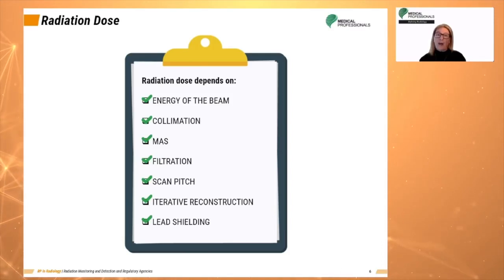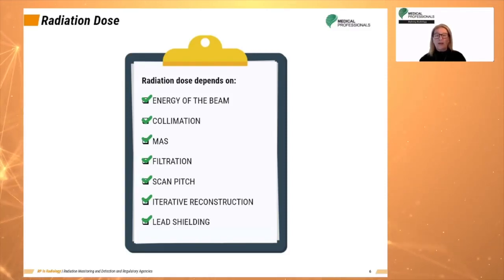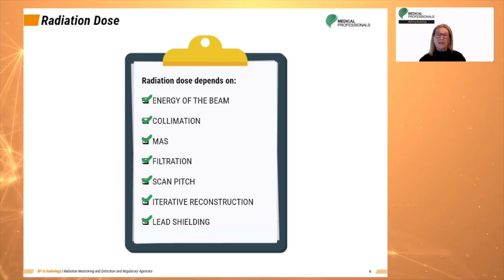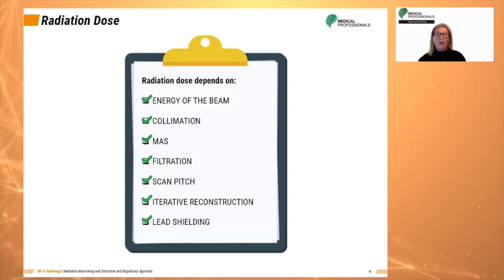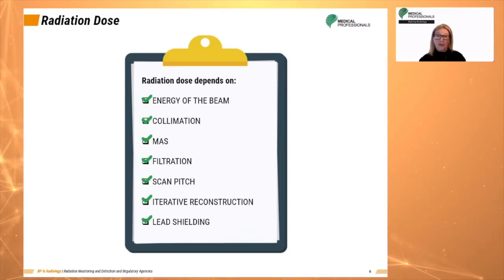The pitch is the way in which the continuous spiral of the scan is stretched out or compressed. It is defined as the ratio of the scan table increment, otherwise known as BI or bed index, per 360 degrees of x-ray tube rotation to the slice thickness or slice width. When the pitch ratio is higher, patient dose is reduced.